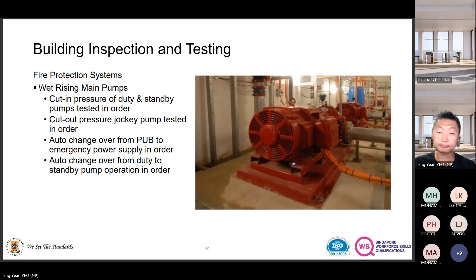For the wet riser, they will do their pressure and flow rate test. Statically, with nothing moving, it's less than 8 bar. So it must be less than 8 bar. They will actually test this with nothing moving. But when we talk about running pressure, it's about 3.5 to 5.5 - that's the so-called running pressure.